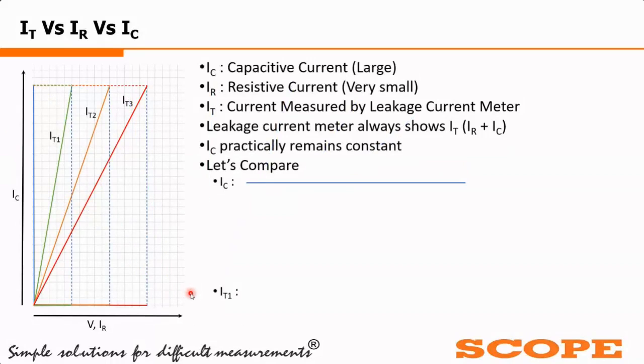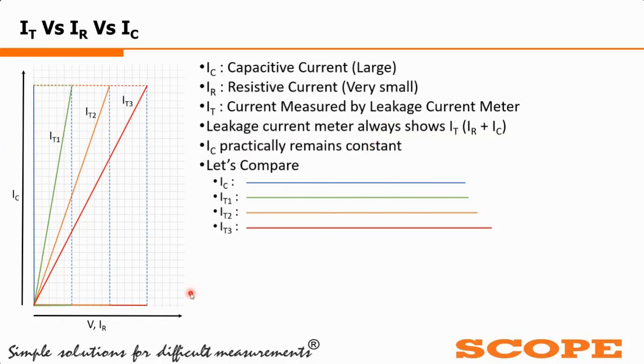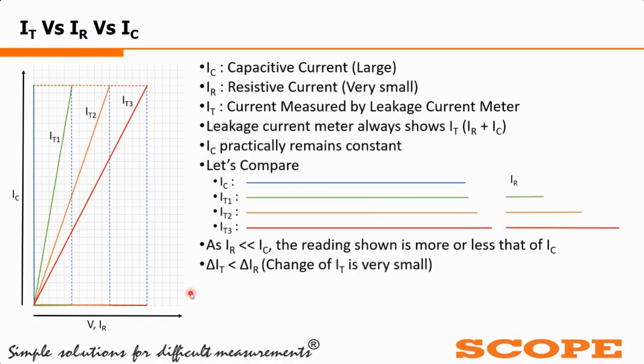Let's compare how the total current has changed. So we are bringing all the things in the horizontal direction, as we can see on the screen. IC, IT1, IT2 and IT3. These are the currents. Practically there is a very small amount of change, as we can see. Whereas if we compare the IR values in this time period, IR has practically become 300% of the earlier initial value. So as IR is very small compared to IC, or the resistive current is very small compared to the capacitive current, the total current reading shown in the surge counter leakage current meter will be practically showing the value of IC only.